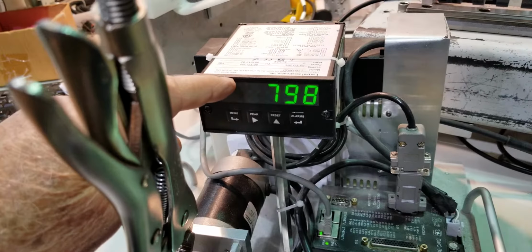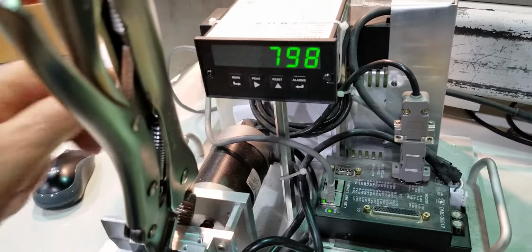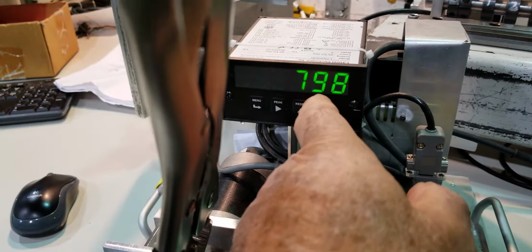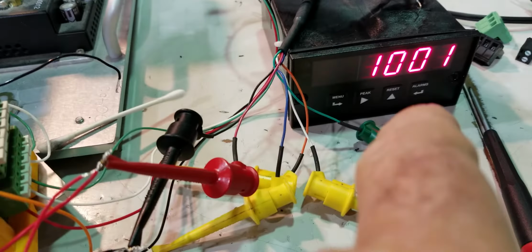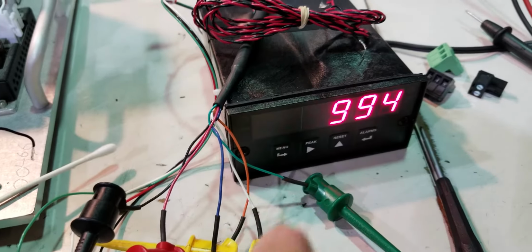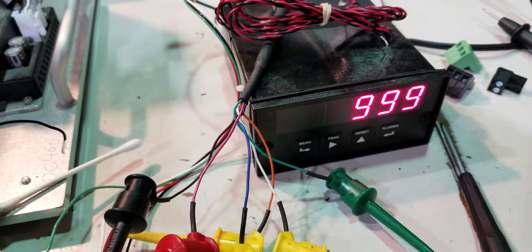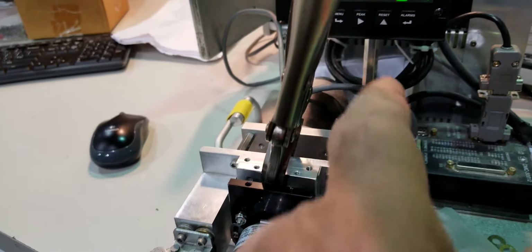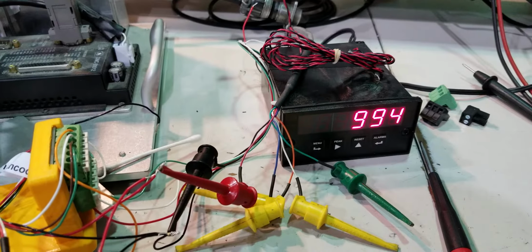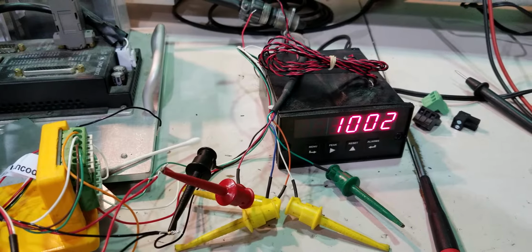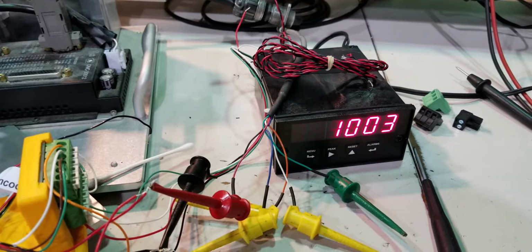This meter is reading the motor controller encoder, while this meter here is reading this encoder here, which is a driven encoder. Ideally, I have this set up so that it's 798 counts per second, which this is trying to control to. I should be seeing 998 counts per second on this display, since this display should read 1.25 times what this display reads, simply because of the difference in the 1,250 count encoder versus the 1,000 count encoder. However, although it's not controlling perfectly, it's within maybe 5 to 10 counts or less of being perfect here, 998.